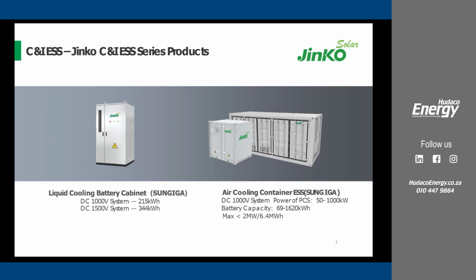We're going to go deep into the C&I energy storage solutions, for commercial and industrial, and we have two sets of solutions. One is the air-cooled battery containers, which is very common - the Sun Giga air-cooled battery containers. Usually this is low voltage, less than 1,000 volts systems, with PCS ranging between 50 to ideally 500 kilowatts, which can be extended to 1 megawatt by paralleling maybe 2 of 500 kilowatts.